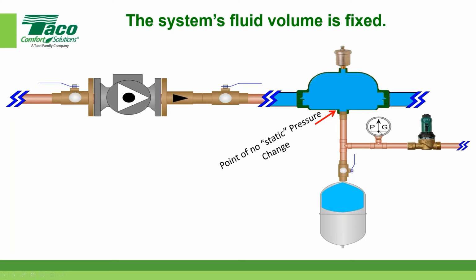If that gauge were to move by that circulator coming on, wouldn't some of this water, remember the water is full, there's no air in the system whatsoever, then some of this water would have to move down this pipe, right? It'd have to be pushed down the pipe in order to change pressure on this. I think you can agree with that. Hopefully you can. Hope you can see it my way. Again, this has been proven over and over again.